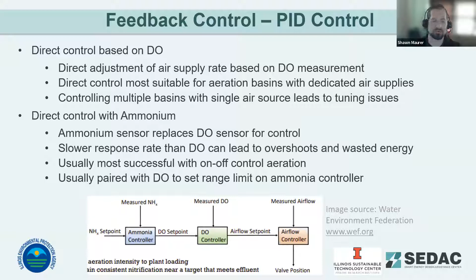What we're starting to see now in marketing and things is feed forward controls, advanced controls using modeling programs, predictive logic, and artificial intelligence, which Zia will touch a bit more on in detail in his presentation. But just as a basic overview, one of the things, again, is ammonia-based control. You've got an ammonia sensor sensing things coming into the plant that's adjusting set points for a DO sensor in your basins. But the actual DO isn't being measured. There's a model that's adjusting those set points depending on what's measured in your influent water coming in. The model has to be accurate for proper function, otherwise you can get wide swings in your aeration set points and unstable function.